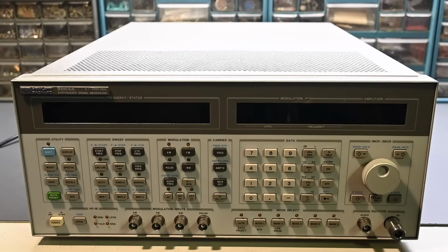When this does the calibration routine, the constants are stored in the memory. And when you turn the instrument on, normally it shouldn't run the lengthy calibration routine. It should just power up and be ready to go because it remembers the previous settings. Now, if it detects drastic temperature changes, it will rerun the calibration process. So I'm curious to see when I turn the instrument on a second time here, and this has been sitting now a full day, if it's able to retain the memory or does it try and run the calibration routine again.